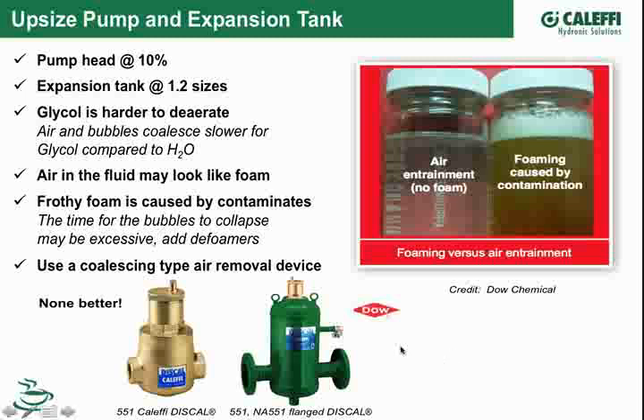From a Caleffi standpoint, if you want to get this air out quickly, this type of air separator with the media in there, as opposed to just a scoop ramp or a small flow-type air vent, is going to do a better and quicker job of getting those little bubbles out as they pass through.